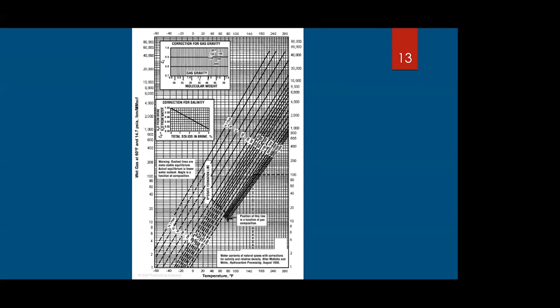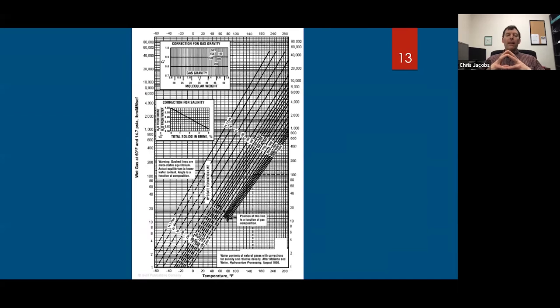Okay. Professor Chris, there is another question here. Why do we use carbon dioxide in the dew point tester? Okay, we use carbon dioxide because it is fairly inexpensive. It is generally environmentally friendly. And because, like I mentioned, when liquid carbon dioxide expands and turns into a gas, it can cool something down very quickly. So it doesn't take a long time to cool down that chamber.